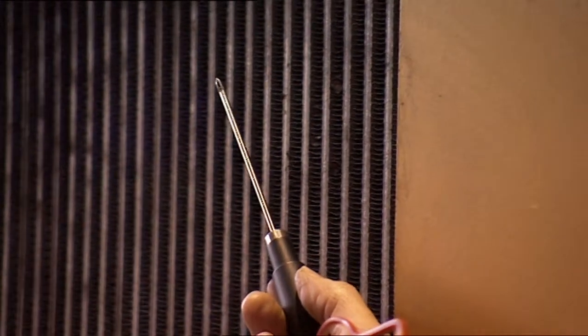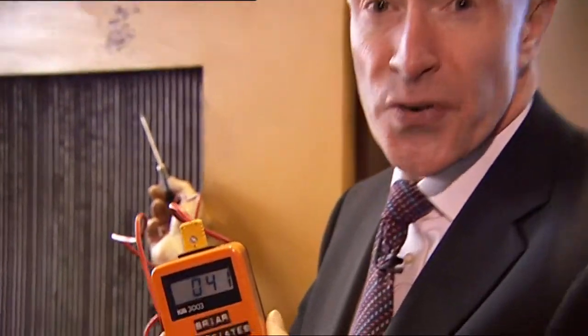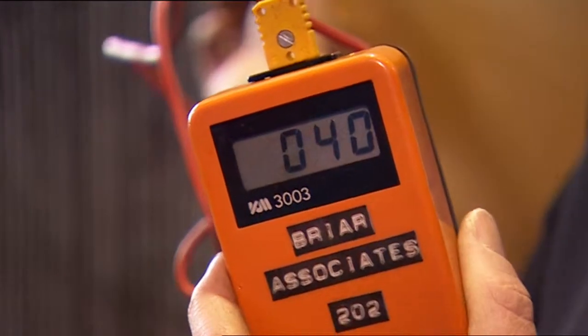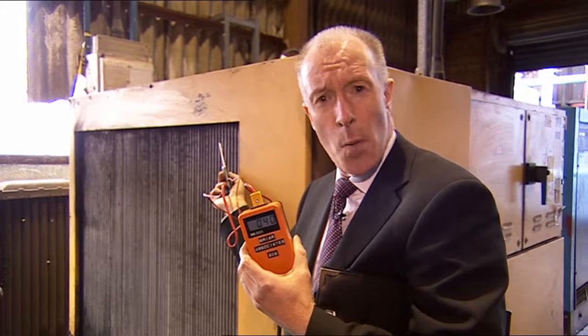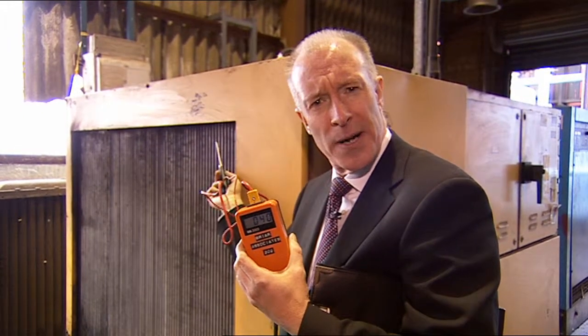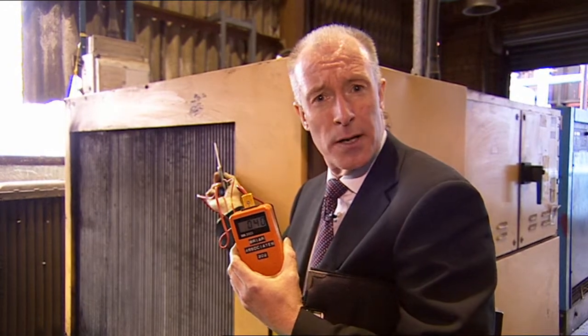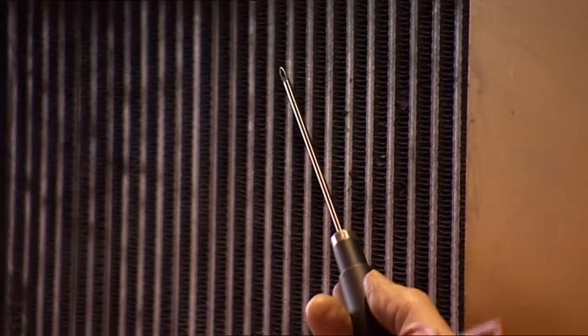The majority of energy that goes into a compressor comes out as waste heat, almost 90% of the energy. Here it's usefully coming out at over 40 degrees C. That's fantastic warm air for heating your factory or your warehouses. So when siting your compressor, consider where you can use this waste heat usefully throughout the winter. In the summer, just duct it out. So the tip here is, when siting a compressor, consider getting the fresh air onto that compressor and making use of the waste heat.